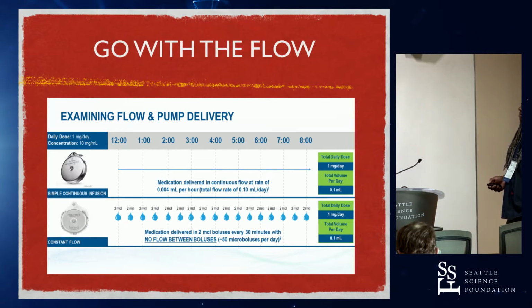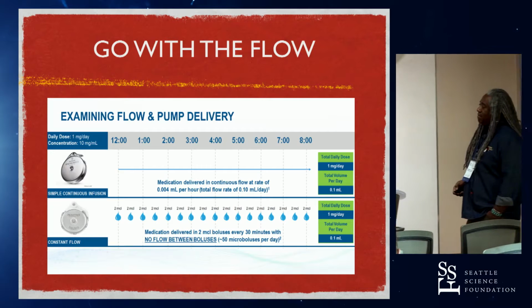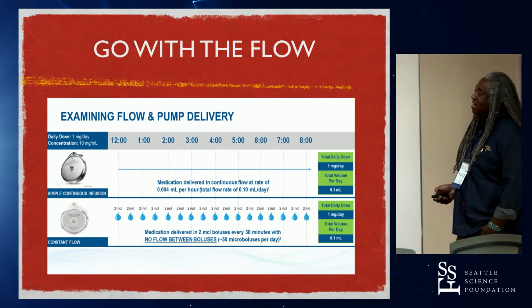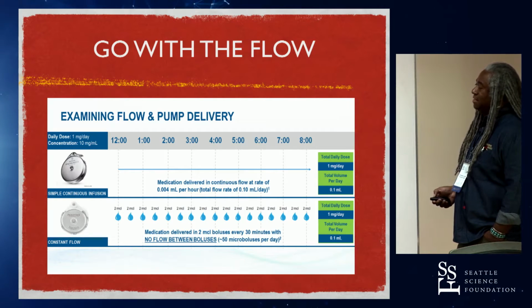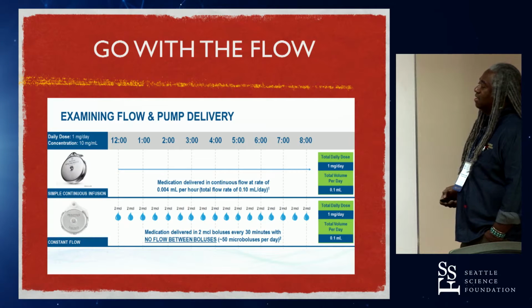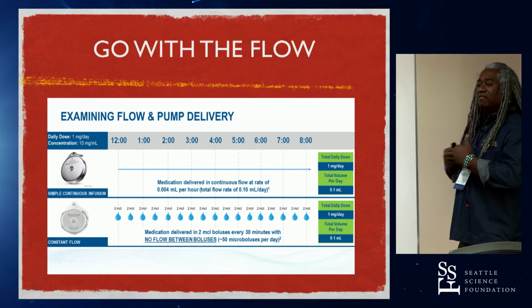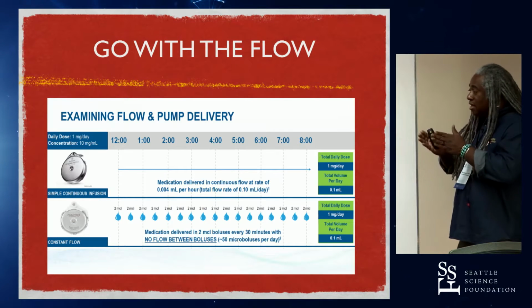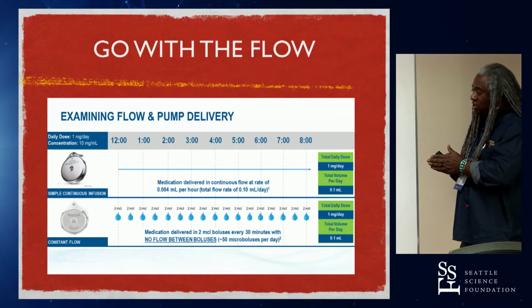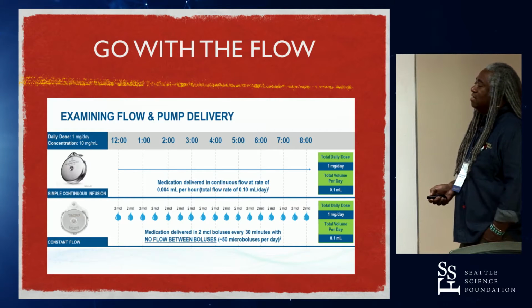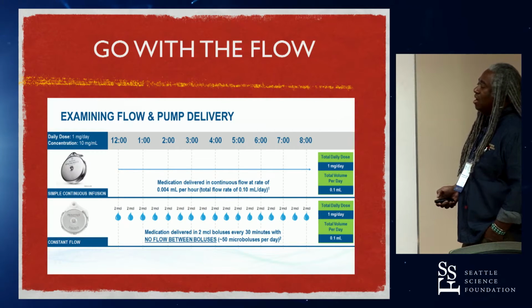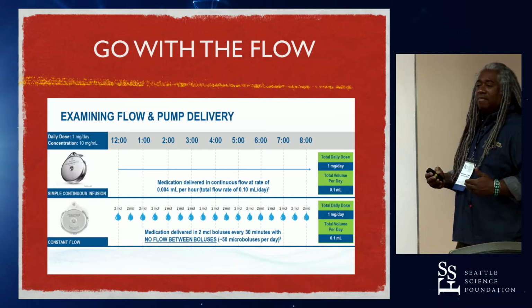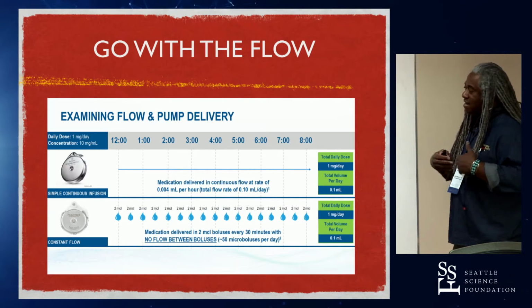To see what I'm really saying, if you were to take a concentration of 10 milligrams per ml of, say, morphine, and you were to deliver a milligram per day, in the Medtronic pump that's delivered as a constant rate. However, in the Flowonix pump, based on the fact that it's delivered in those boluses with complete closure and no drug delivery between those boluses, you're getting these microaliquots. So you're getting 2 microliter boluses every 30 minutes. That affects how the medication is delivered.